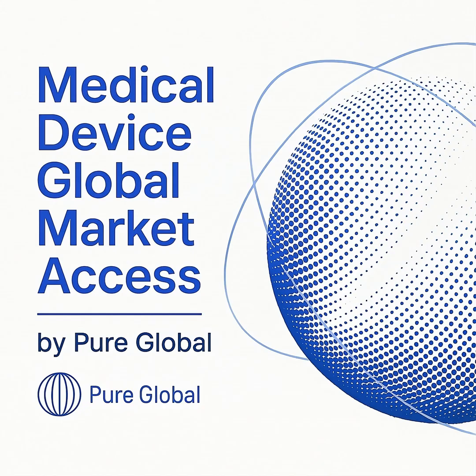A frequent question we encounter is from manufacturers who have secured FDA registration in the United States and want to know what is required to enter the Indian market. A common assumption is that FDA approval might serve as a fast track, but the regulatory landscape is more nuanced. While beneficial, U.S. FDA approval does not replace the need for a specific import license from India's own regulatory authority, the Central Drugs Standard Control Organization, known as the CDSCO.